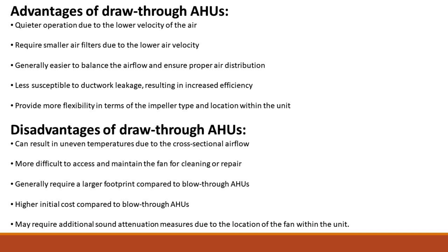Disadvantages of draw-through AHUs: can result in uneven temperatures due to the cross-sectional airflow; more difficult to access and maintain the fan for cleaning or repair; generally requires a larger footprint compared to blow-through AHUs; higher initial cost compared to blow-through AHUs; and may require additional sound attenuation measures due to the location of the fan within the unit.